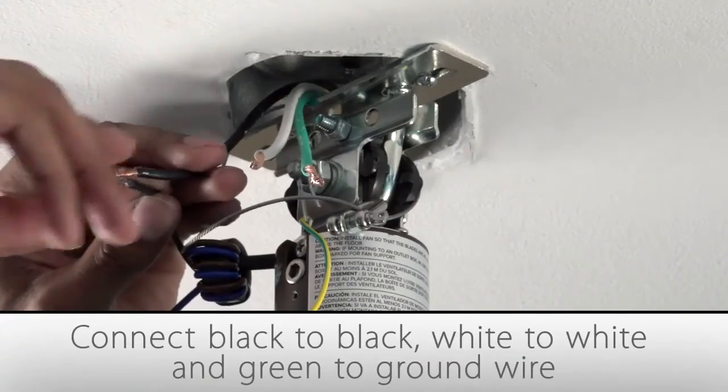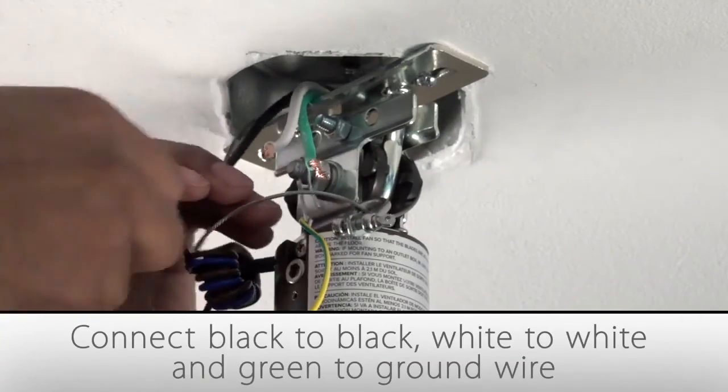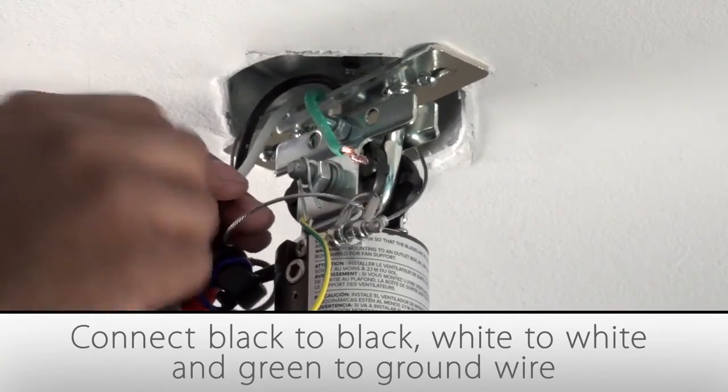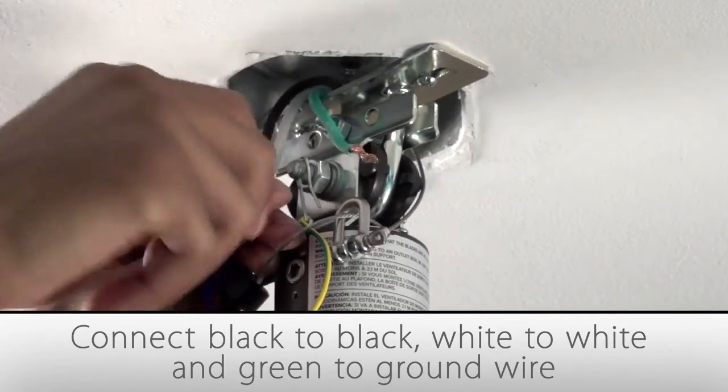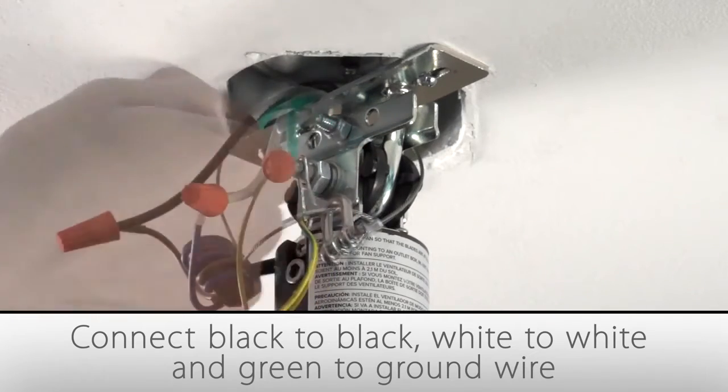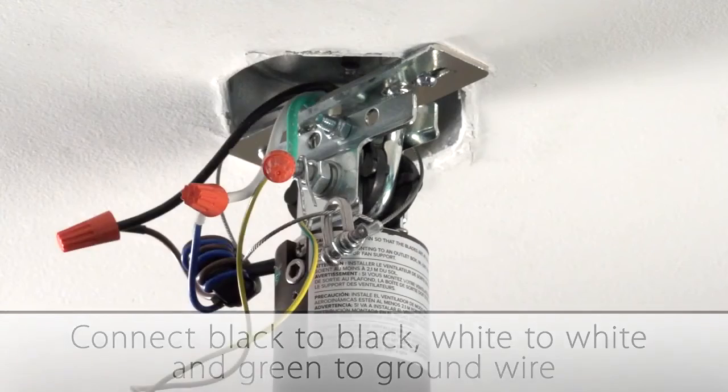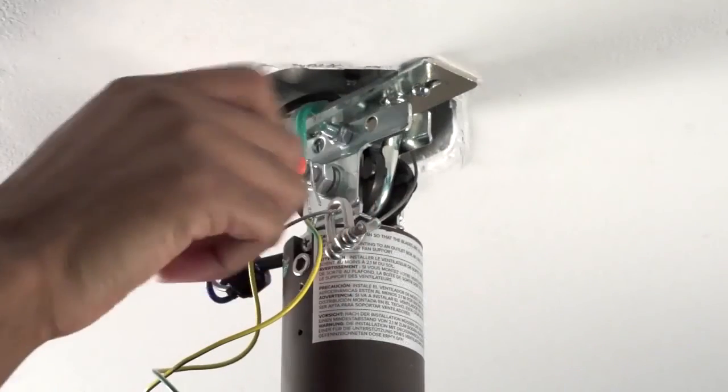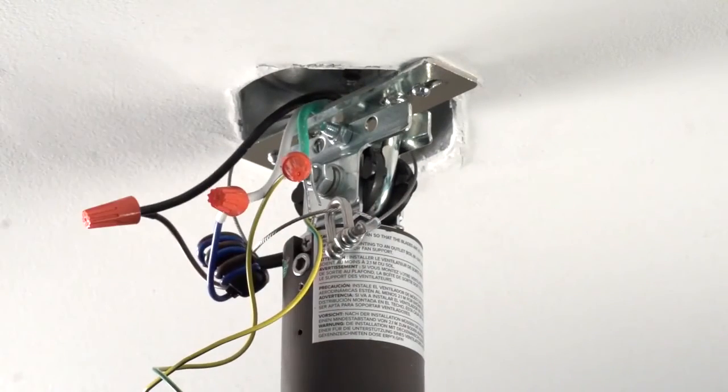Next, you will connect the fan wires to the supply wires. Twist the ends together securely and secure the connections with wire nuts. Match black wire with black wire, white with white, and the green ground wire to green or copper wire. Test the wire connections by lightly tugging on the wire nuts.